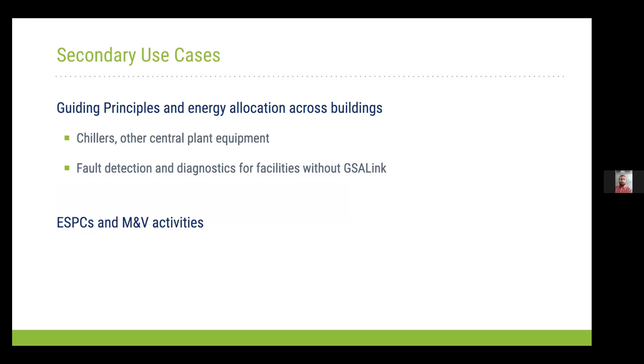Secondary use cases include something we've identified regionally as a need that hasn't been easy to address previously: monitoring energy usage from central plant equipment. This came up through our guiding principles programs and general energy allocation, especially in campus settings with central chiller or boiler plants. Being able to monitor energy usage to those chillers and install BTU meters downstream allows us to accurately allocate usage to each building and get proper EUIs, which is critical for guiding principle certification.